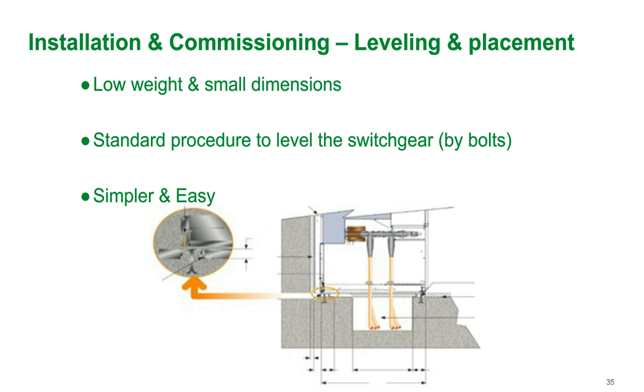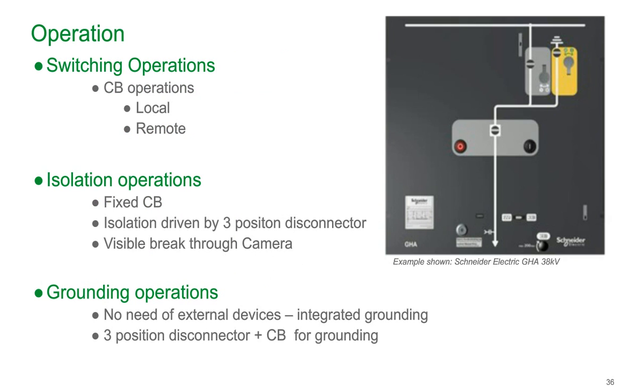Operation of GIS is very straightforward. Typically there's an active mimic bus on the front of the switchgear, so this picture here shows our GHA, gas insulated switchgear, for 38 kV. So you have a single line diagram showing your circuit breaker open and close indication, and also your isolation and grounding switch. You have an integrated grounding switch in each section of GIS.